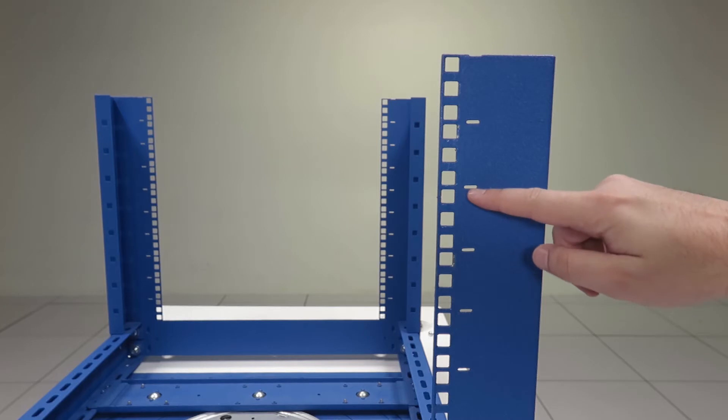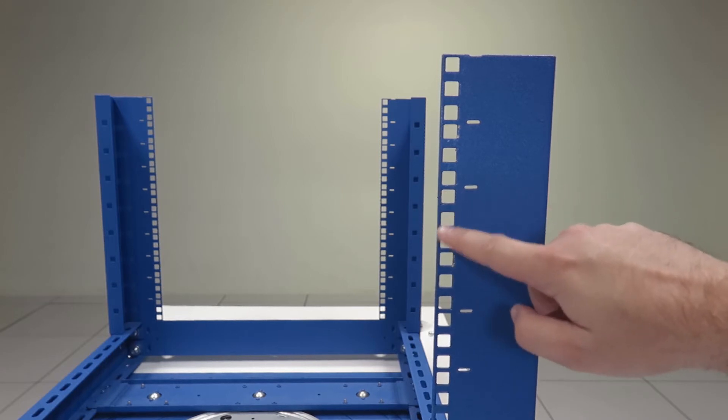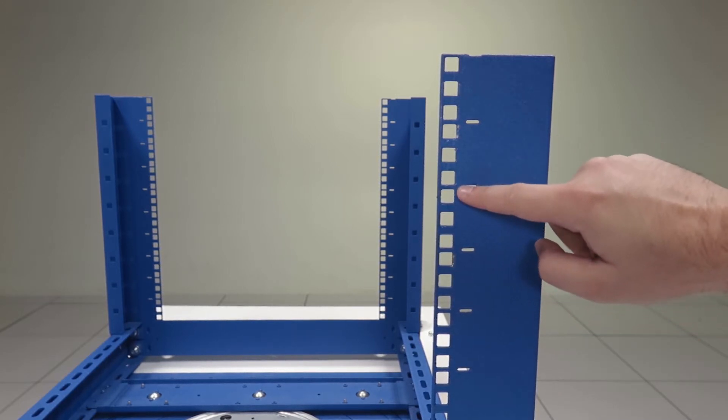This square hole rack has slots on it which aren't used for anything other than indicating where each U space stops and starts. Between each slot, there are three square holes which make up one U in space.